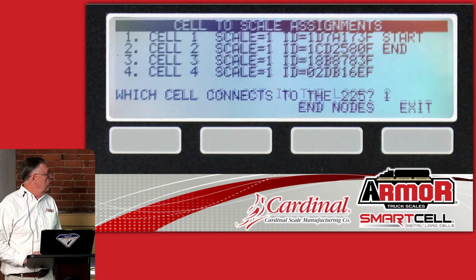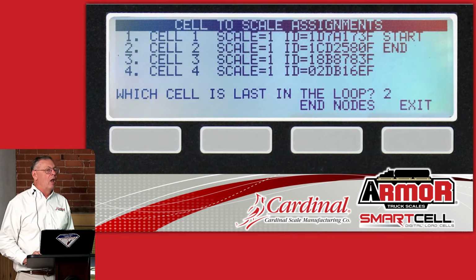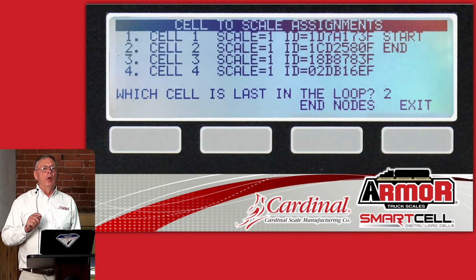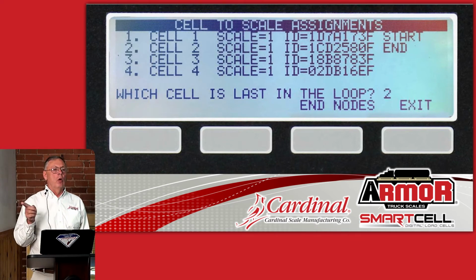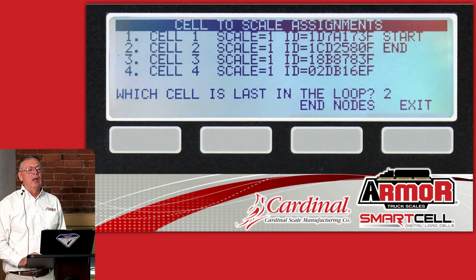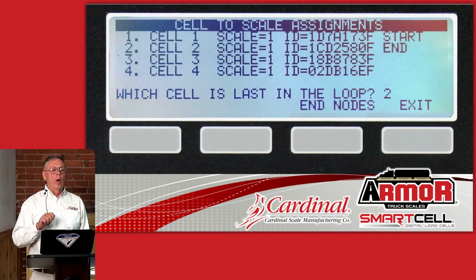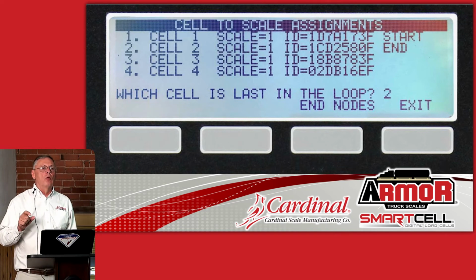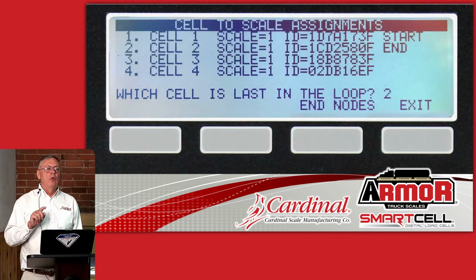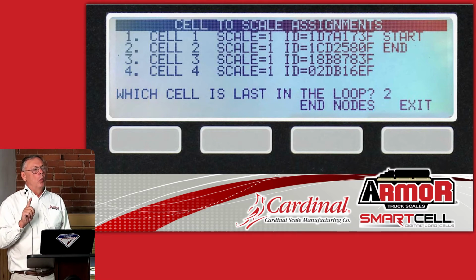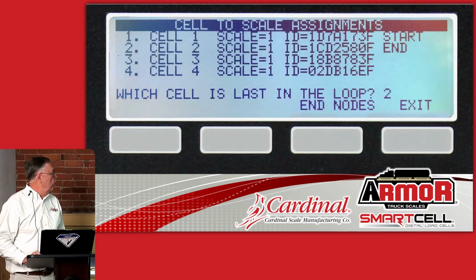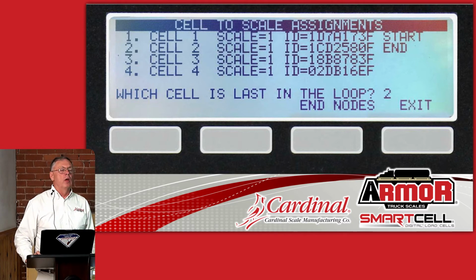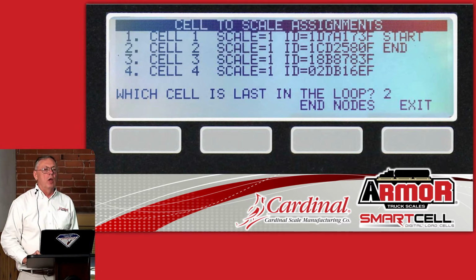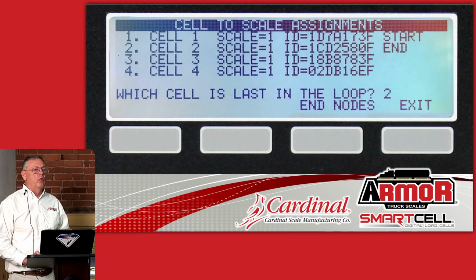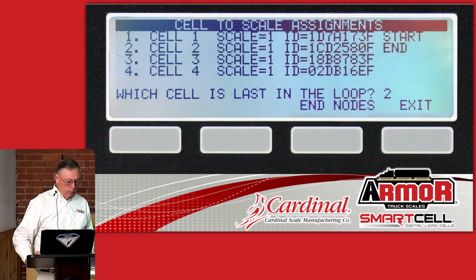You enter that, and then it says which load cell is the last in the loop. We don't really know if you're going to take the loop around the scale clockwise or counterclockwise, and again, we don't care. Just tell us where the end of the loop is. There's an end node connector you install there, and that way we can normally tell you when there's a break in the cable where that cable would have a problem. And that's the only thing really at installation that the technician should do, tell us the first of the loop and the last of the loop.